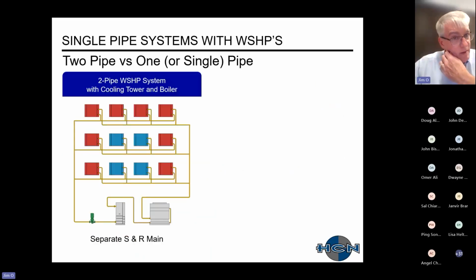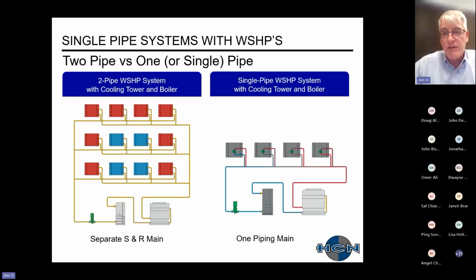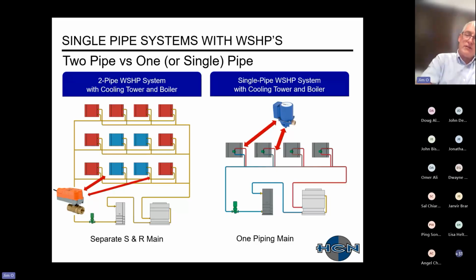So on a 2-pipe system, you have supply and return with just a single water source heat pump system. As expected, you have a single main that goes around and serves as your supply and return. You can see once again why these are attractive, as you're eliminating a whole other piping main. For renovations with core drilling, etc., it might make it much easier to implement versus a 2-pipe system. And then once again, on a 2-pipe system, you have control valves at each of the water source heat pumps as they turn on and turn off. In a similar situation, but instead of a control valve, you have a small circulating pump that will turn on or turn off based on whether your unit is in heating or cooling mode.